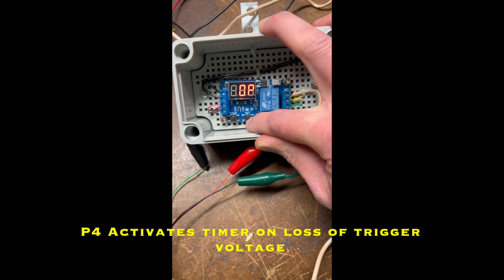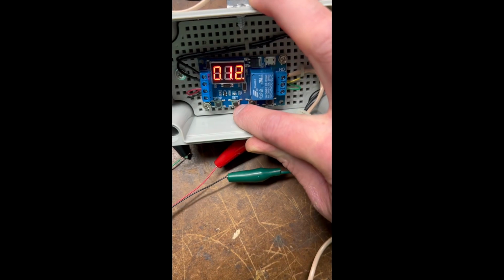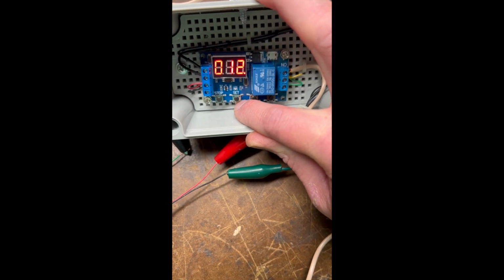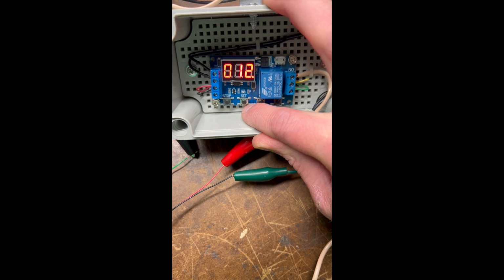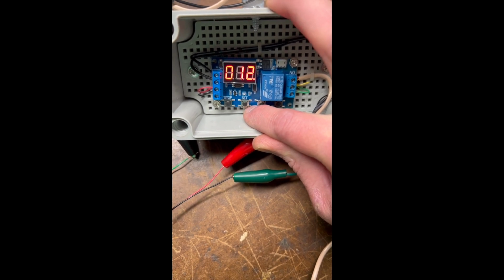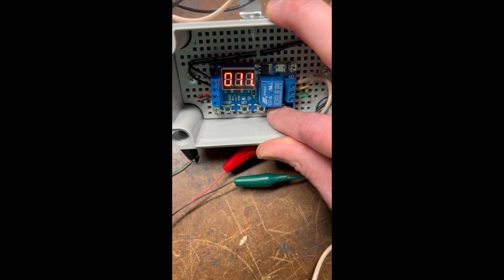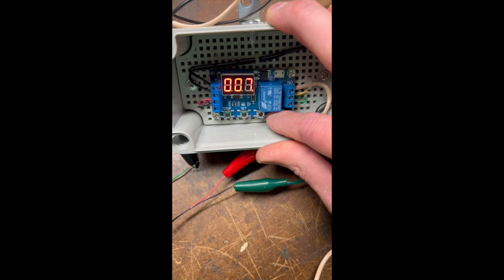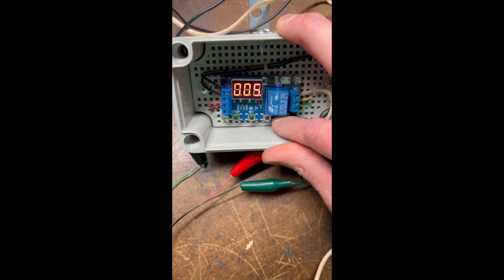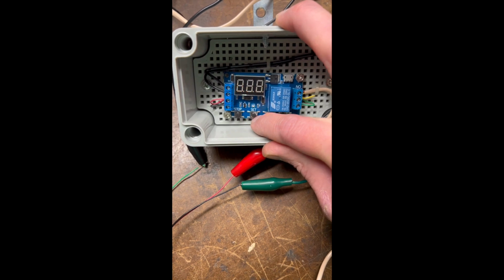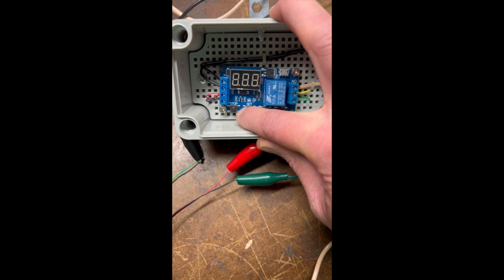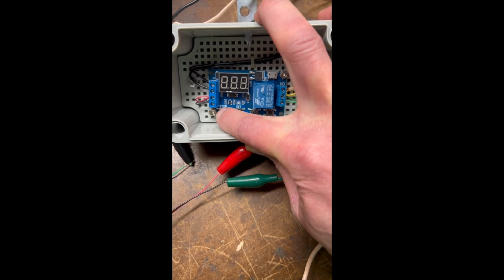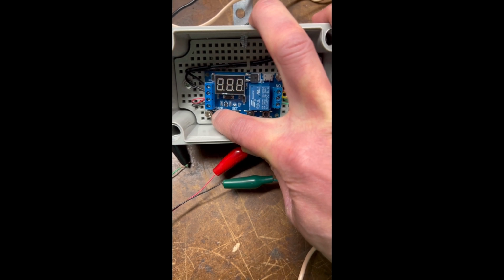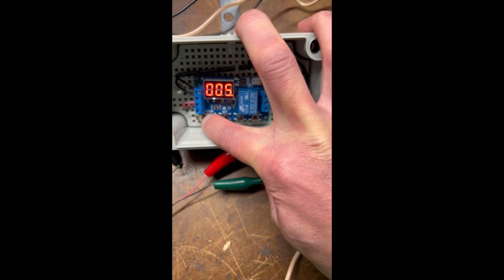This is my timer, my OP timer, currently set for 1, 2, and you can see that the decimal is all the way to the right, so that's 12 seconds. I'm going to put it down to 5 seconds for this purpose. If we hit the combination of buttons, we can get the decimal point to move. The stop button, I believe, moves the decimal point. Yes, it does. So that's 5 minutes, and so forth. So we're going to go back to 5 seconds.